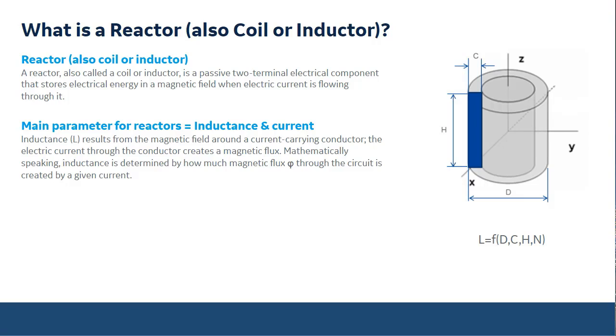I mentioned the conductive material, the aluminum, for example. These wires, or this wire, are separated from each other with some kind of insulation material. In the past, air was used as insulation material. Nowadays, we have paper, we have plastic, we have different types of insulation. So by not having these two wires touching each other, that isolates the wires, and that creates then a turn. So a reactor with more impedance means that the reactor will have more turns, more inductance. More impedance means taller reactors. More magnetic field means more power, more current, and more inductance flowing through. So there are several concepts that shape the equipment, and we got some questions before the call asking about sizing.